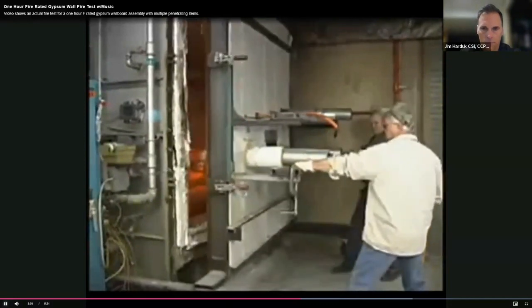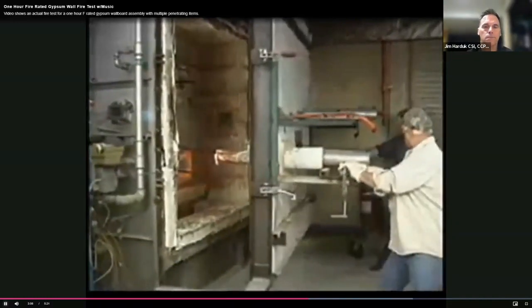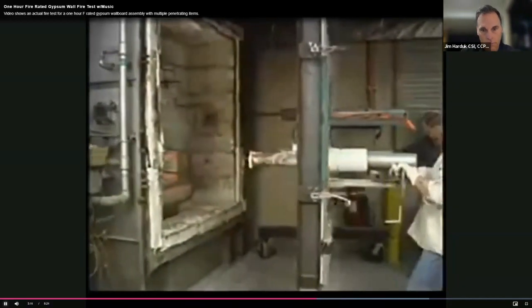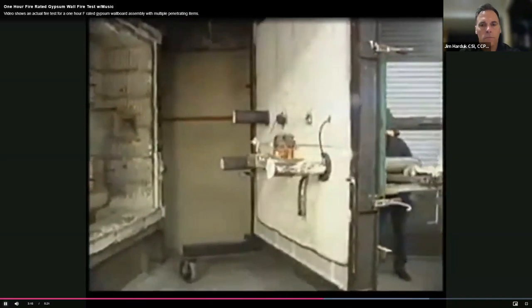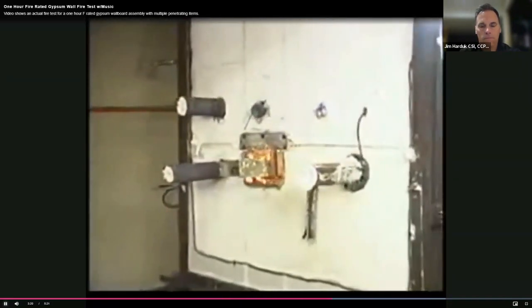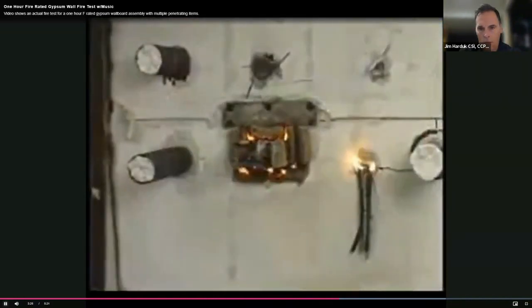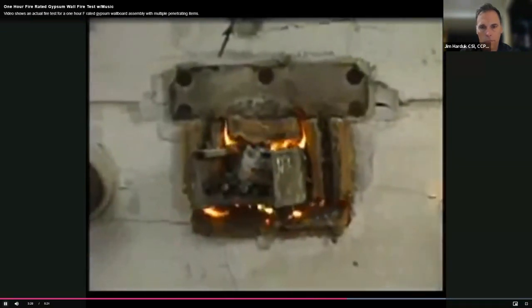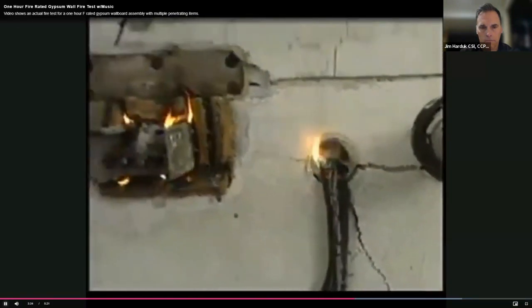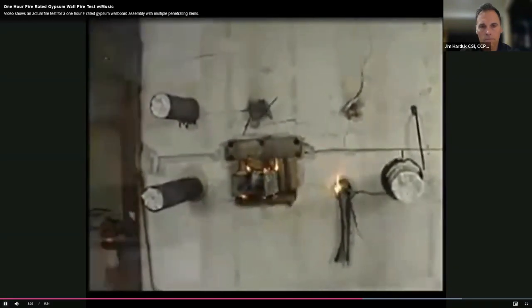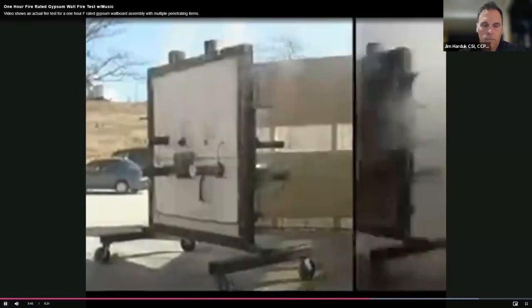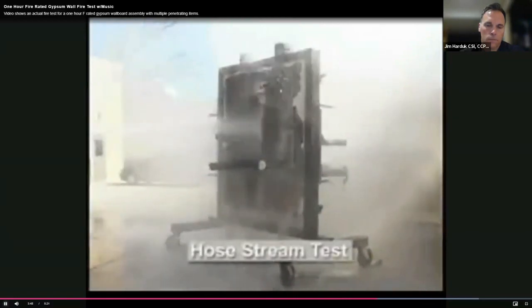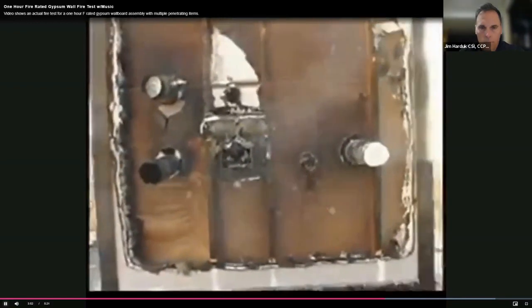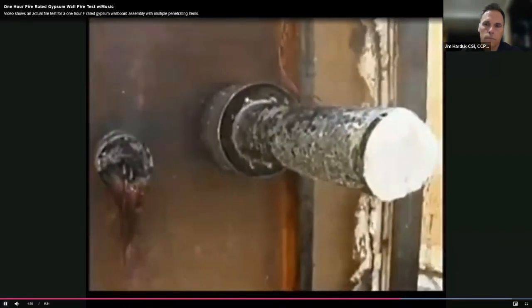The wall is now being removed from the furnace. The gypsum wallboard is cracked and has lost most of its structural integrity on the hot side of the assembly. The wall is taken outside and is hit with the hose stream for a predetermined amount of time per the test standard. For a 1, 2, or 3 hour fire test, the hose stream is run at 30 psi and 20 feet from the test specimen. After the fire test and hose stream, the penetrating items are inspected to see if the fire stop materials have remained intact and have not been dislodged during the hose stream test.